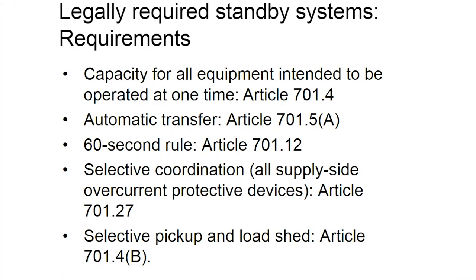The capacity of the generation has to be enough to operate all the loads that were intended to operate simultaneously. This is less stringent than the requirement for emergency systems because it allows for some diversity among loads that won't necessarily operate together, maybe like heating and cooling of the same space or elevators with a controller that allows only one cab to run on standby. The transfer to standby generation has to be automatic, just like emergency loads. The standby system has to apply power to its loads within 60 seconds of the loss of normal power. That's as contrasted to the emergency system rule, where power has to be back on within 10 seconds.